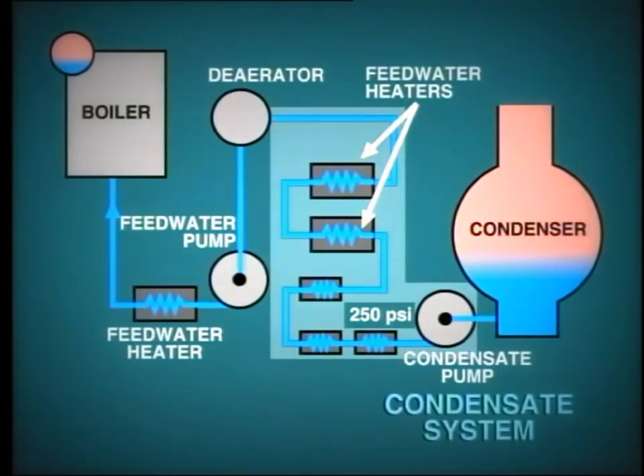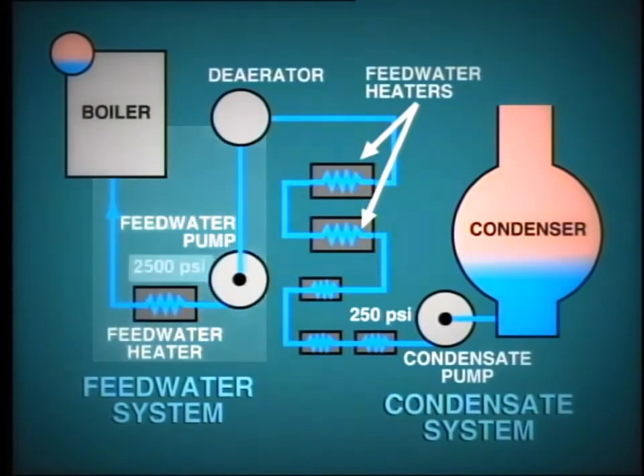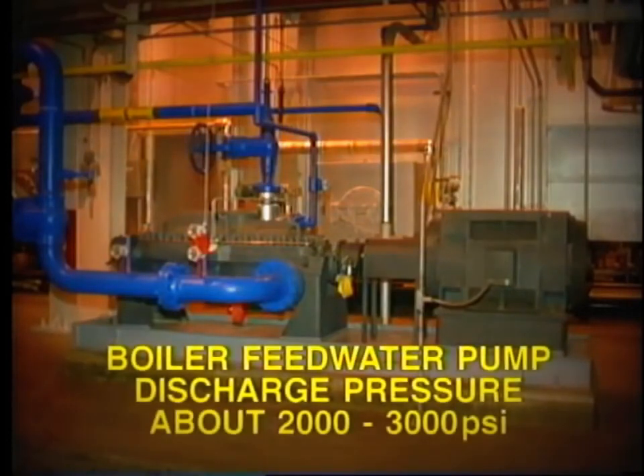From the de-aerator onwards, we refer to the continuation as the feedwater system, which operates at much higher pressure. The pressure developed by the boiler feedwater pump must be sufficient to overcome losses in the piping system plus the pressure in the boiler itself. This means that the boiler feedwater pump discharge pressure must be about 2,000 to 3,000 PSI, depending upon the particular installation.